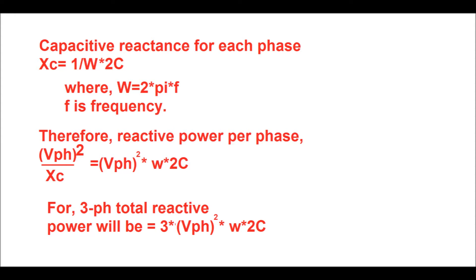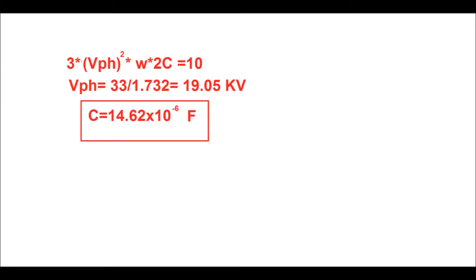We know that capacitive reactance XC = 1/(ω·C), where ω = 2πF and F is the system frequency. Since the equivalent capacitance per phase is 2C, XC = 1/(ω·2C). Reactive power per phase = V_phase² / XC = V_phase² · ω · 2C. For three phases, total reactive power = 3 · V_phase² · ω · 2C. With V_phase = 33kV / 1.732 = 19.05kV and total capacity of 10 MVAR, the capacitance of each unit comes to 14.62 microfarads.